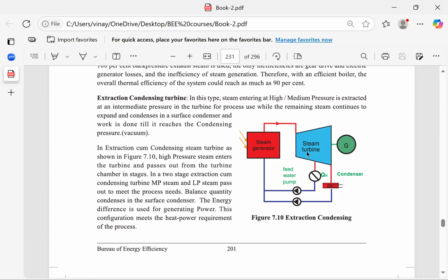So you will have to know or draw a graph indicating at what point which pressure is there. Therefore, when you design, suppose the process requirement is 15 kg steam at 200 degrees temperature, you will have to find the point where it is 15 kg. Here it starts at 150 kg and expands down to that point.